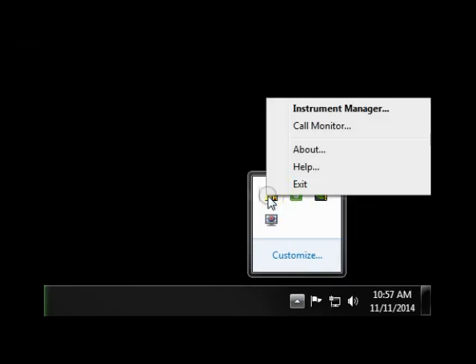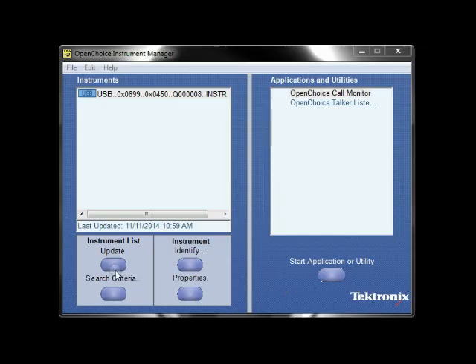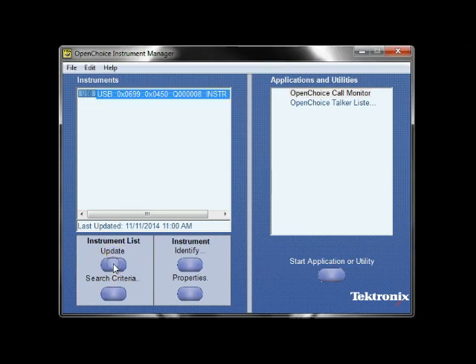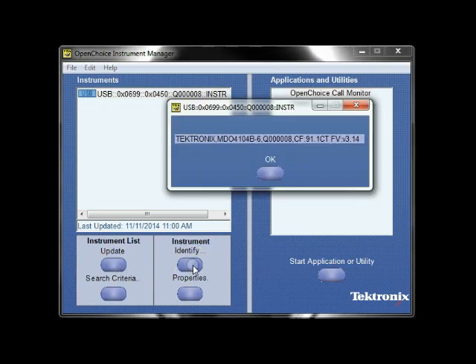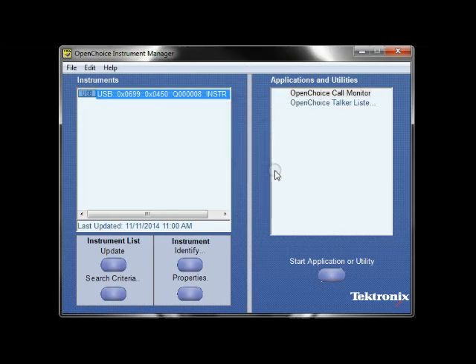On your PC, open TekVISA and enable USB connectivity. You may need to press Update to see your now connected scope. Click on your connected scope and take note of the USB identifier. The firmware version of your scope can also be found when you press the Identify button.